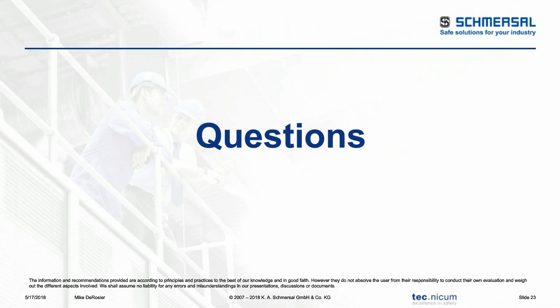All right, next question. Is a lockout tagout required for adjustments and tool changes when guarding is not installed, for example, with vertical manual feed mills? Well, if you go back to the application of the standard, when you look at the application section of OSHA 1910.147, it talks about when it's covered and when it's not covered. So when you don't have any guarding and you're doing a tool change, how do you prevent that machine from unexpectedly starting to fire it up? You need to perform lockout tagout doing tool changes in a case like that. How do you prevent that when there's no guarding?